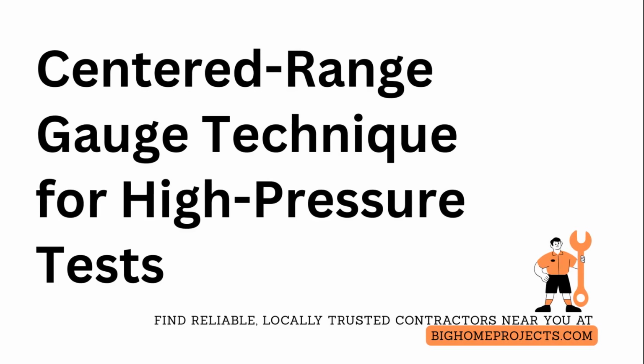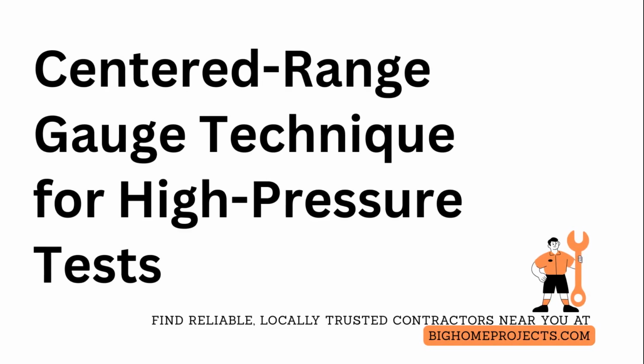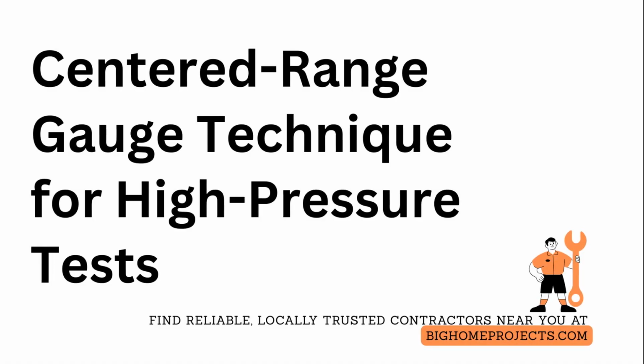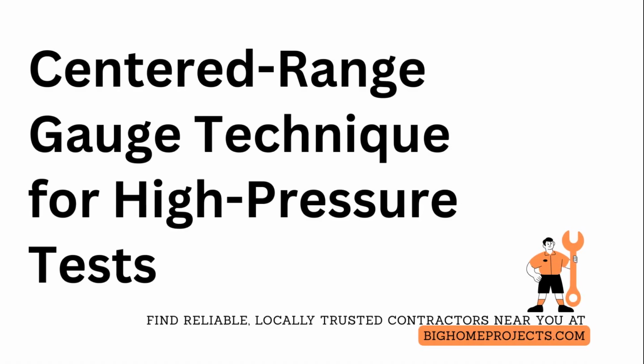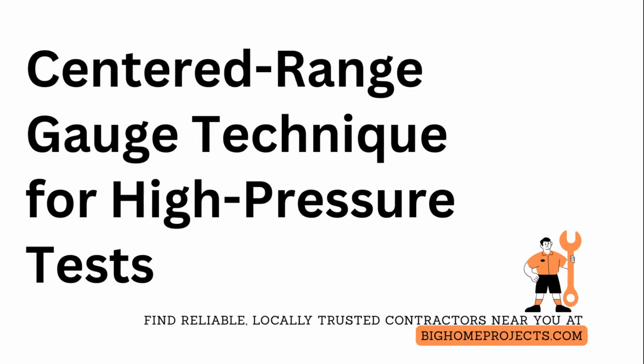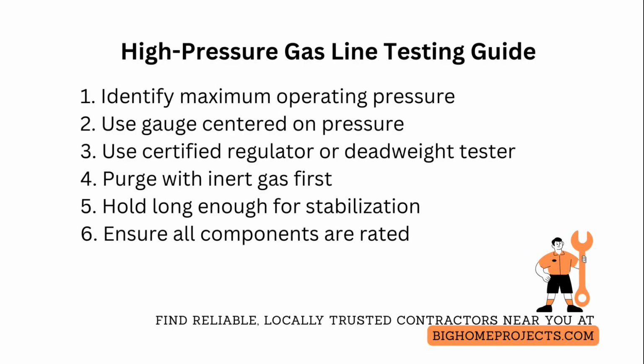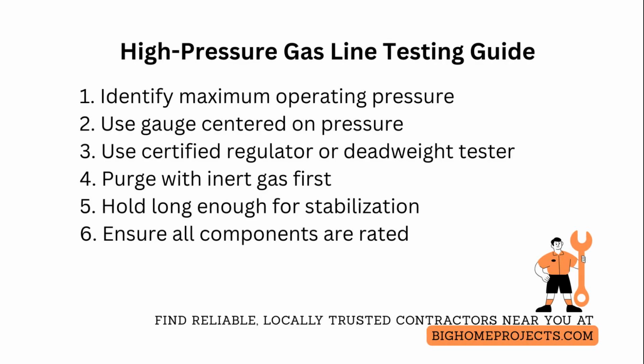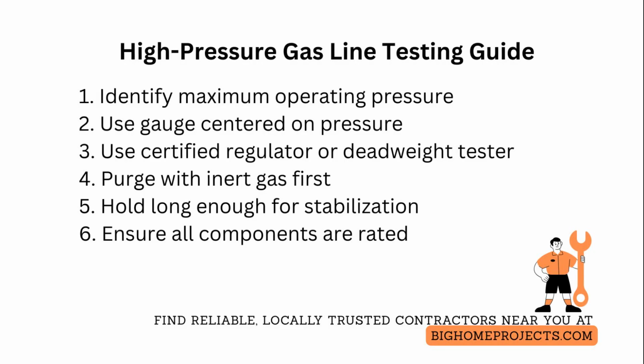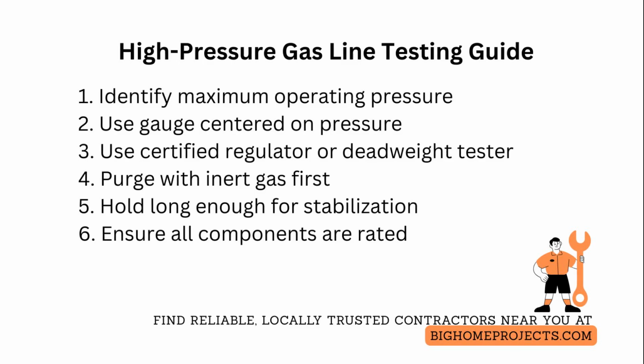Pressure testing high-pressure gas systems requires different gauges, procedures, and safety margins than low-pressure checks, and getting it wrong risks catastrophic failure. When you pressure test a high-pressure system, first identify the maximum operating pressure and use a test pressure that is a defined percentage above that value per code. Typically 10% above for many jurisdictions, but always confirm the local code and equipment manufacturer requirements. Never rely on a one-size-fits-all number.